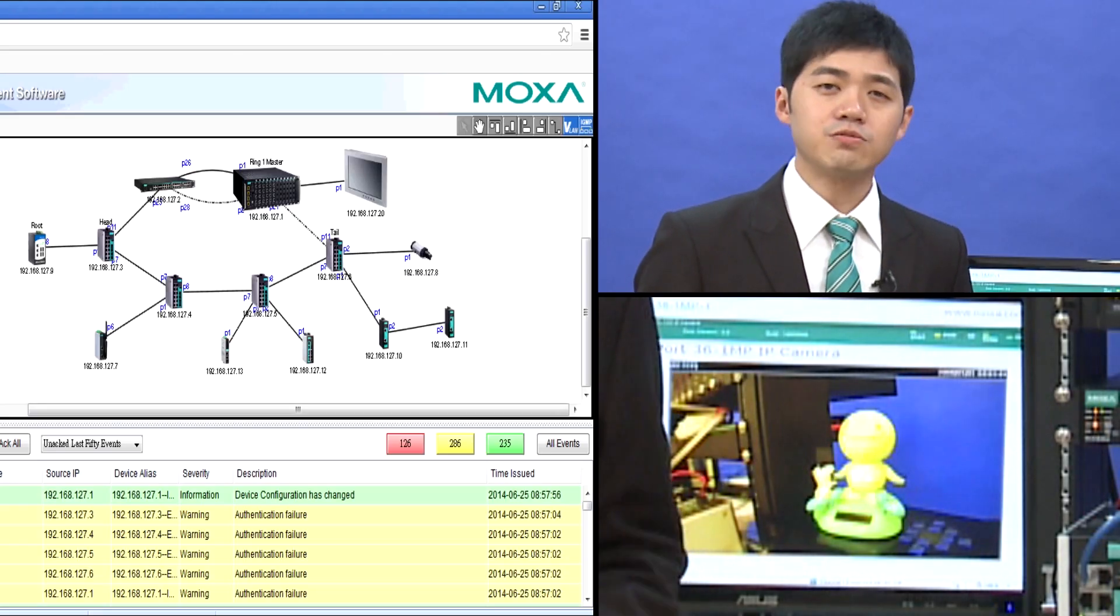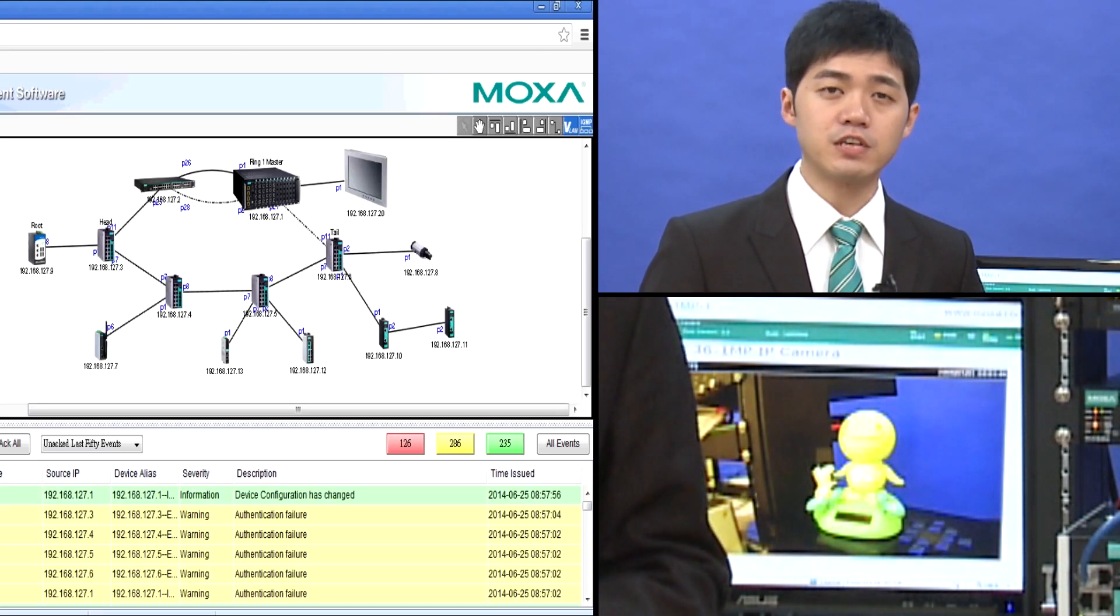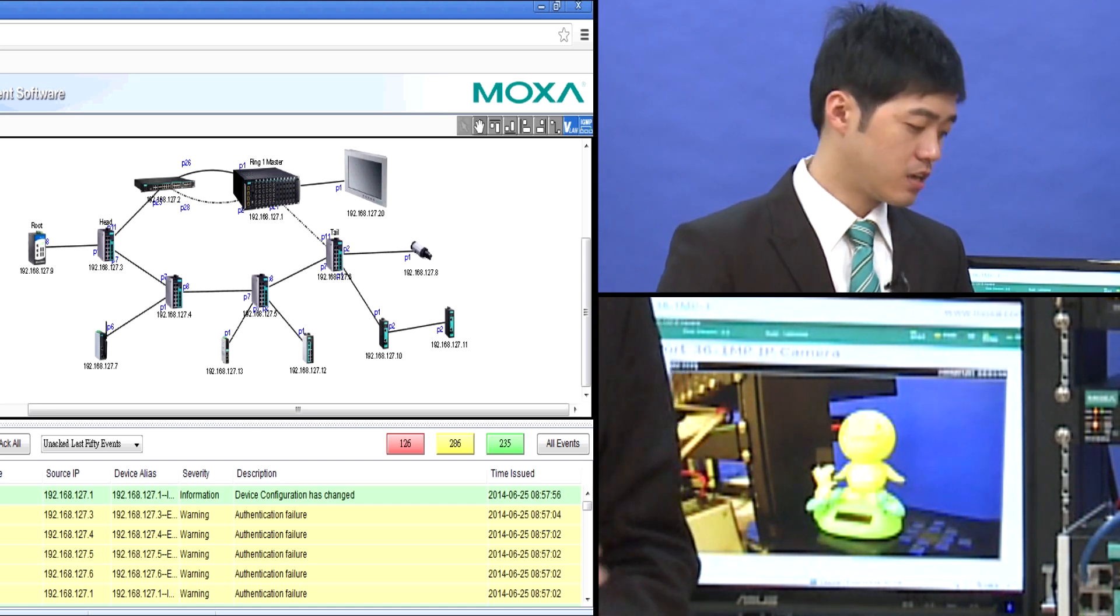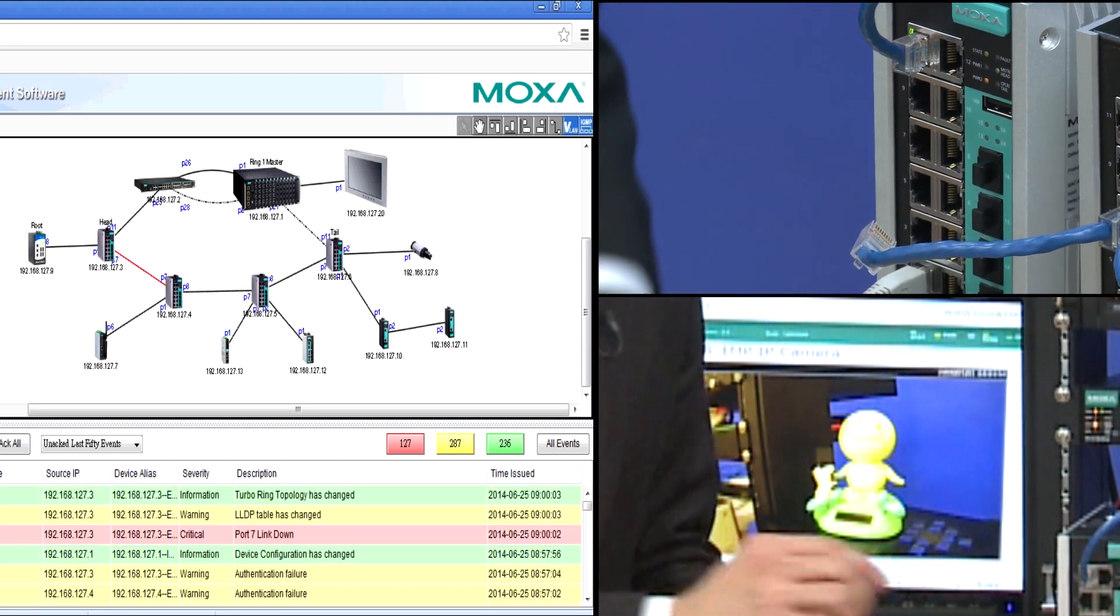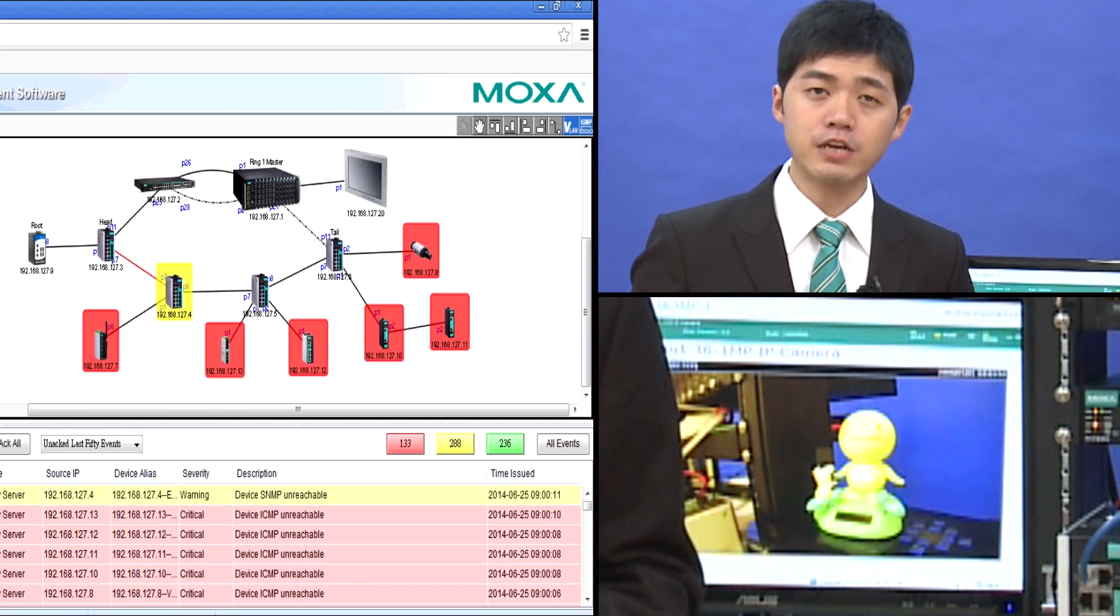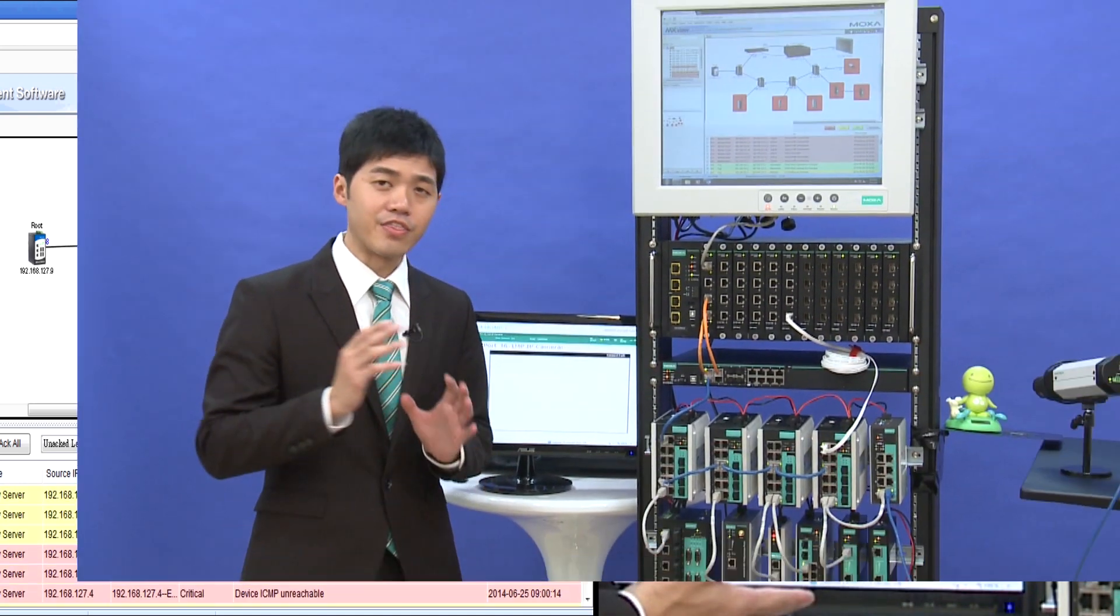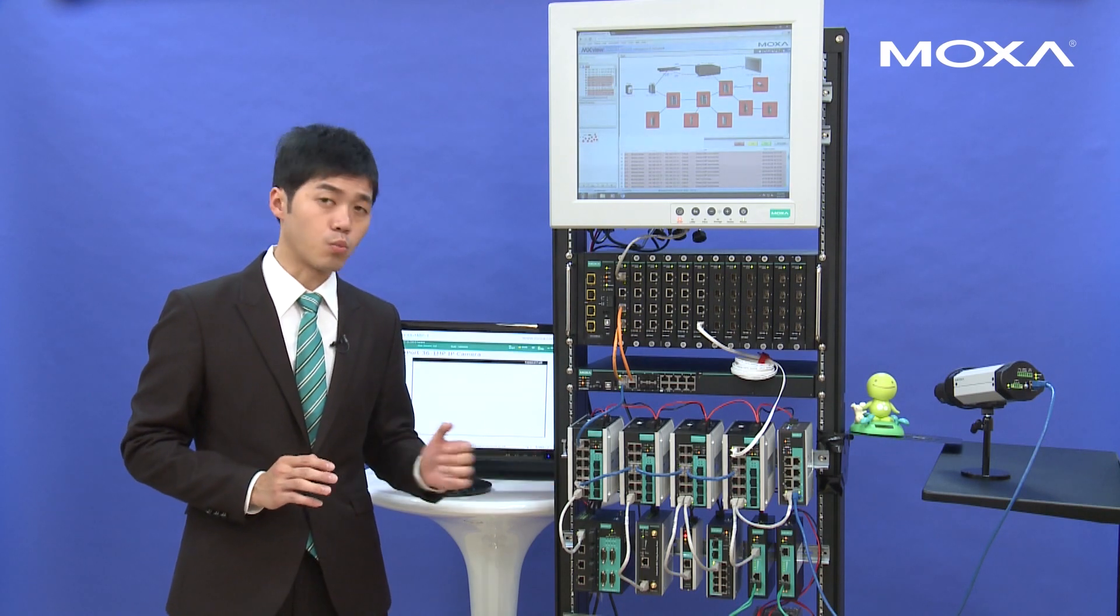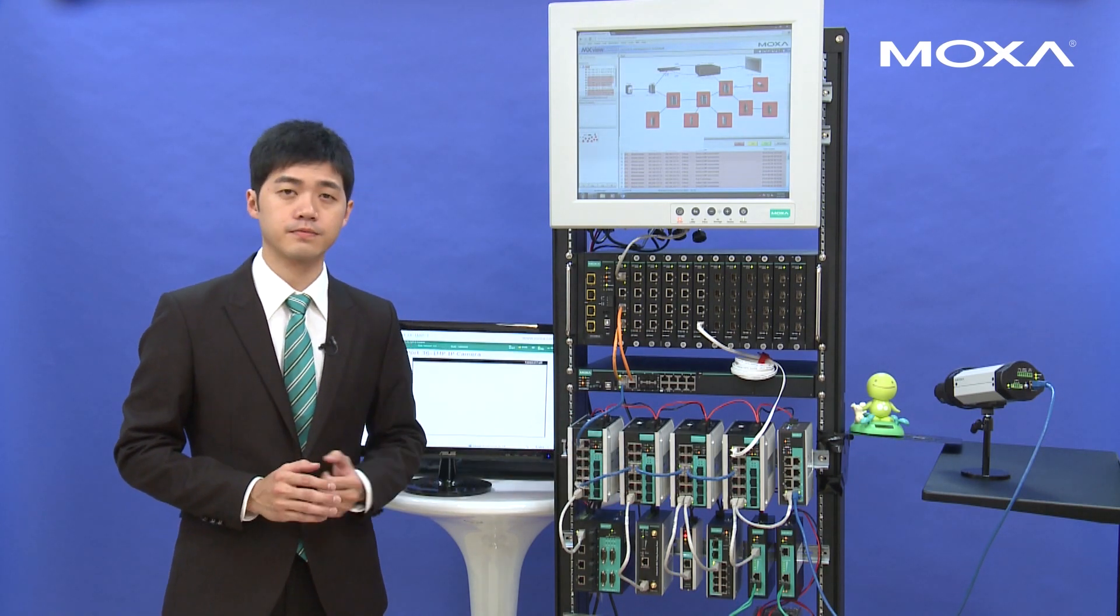As you can see, if the VLAN settings has been changed mistakenly, and unfortunately, if we break down this wire, at first, in the control center, the automation engineer will find the video lost. And they will realize why the redundancy doesn't work, why the turbo chain doesn't work.